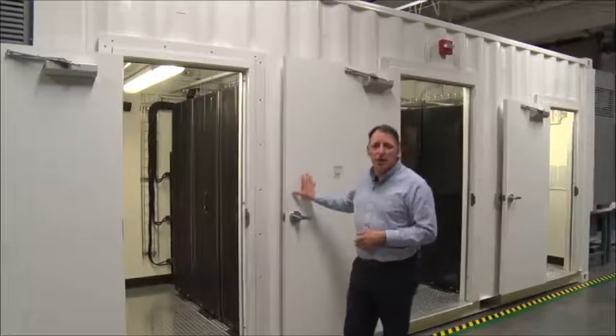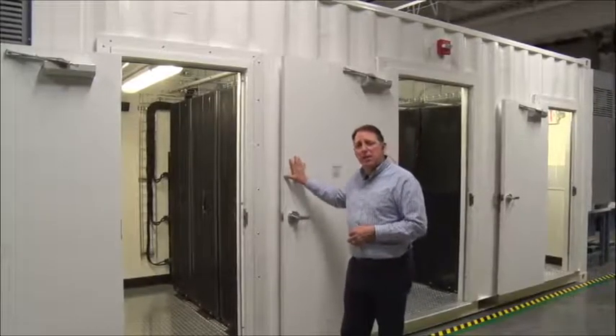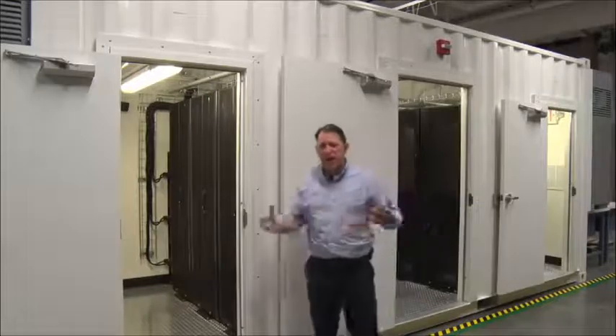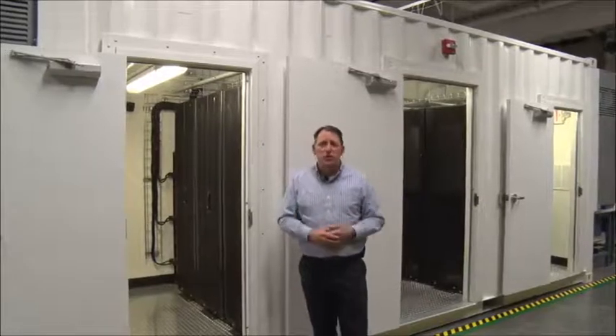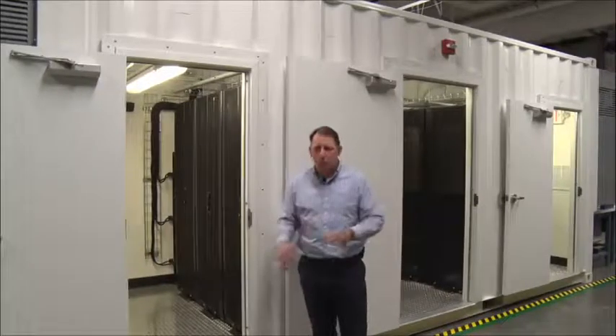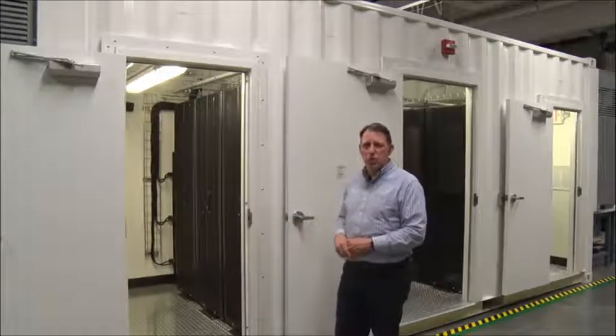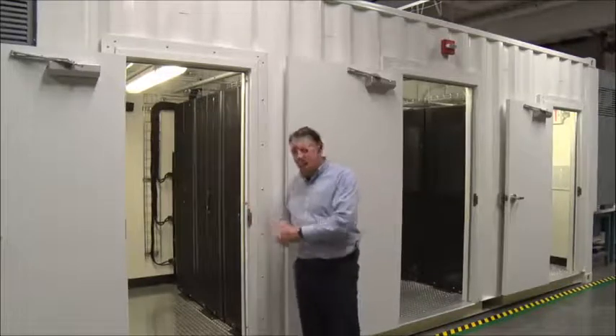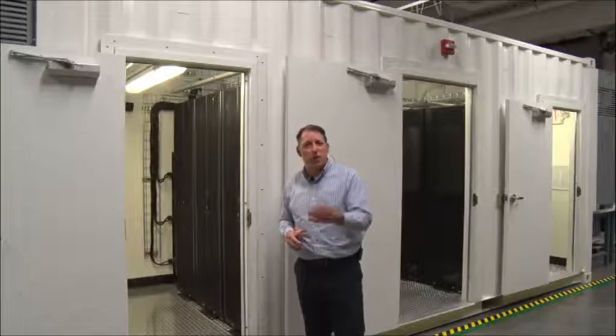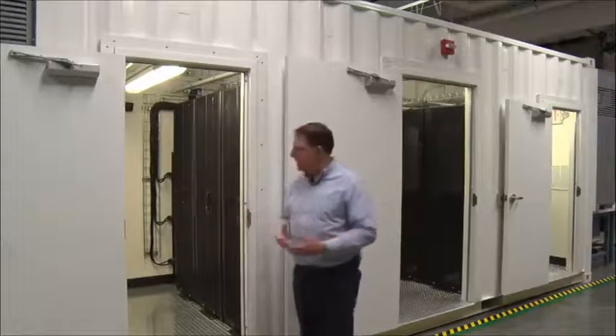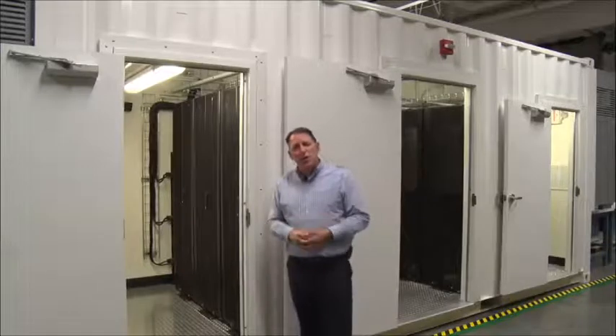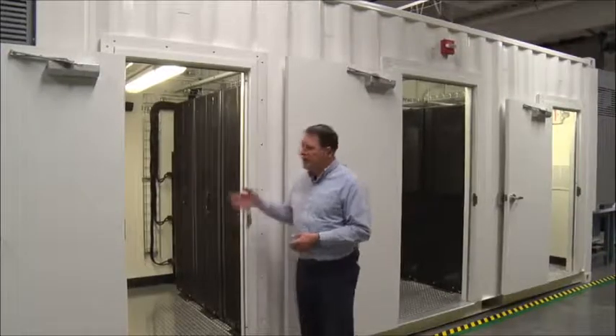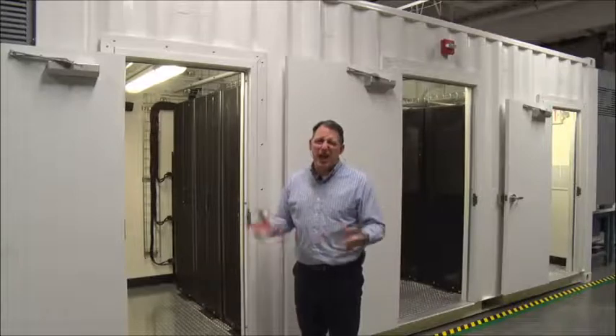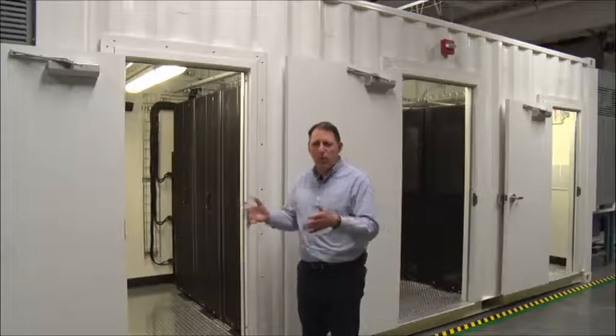One last thing we do with these, we'll make these into power modules as well to address stranded capacity issues where maybe we've got too much white space and cooling but not enough power. We can put UPSs and switchgear in these and deliver some of that power distribution where maybe we don't have enough capability there. So the ISO container is one of the form factors that we build on. Trade-offs are size and width of the unit.